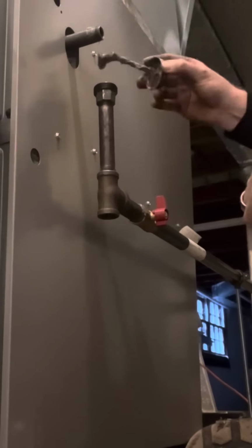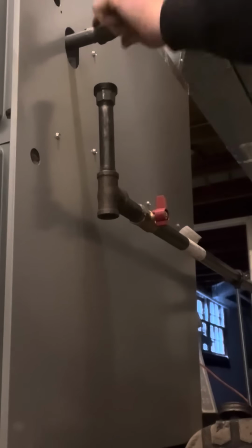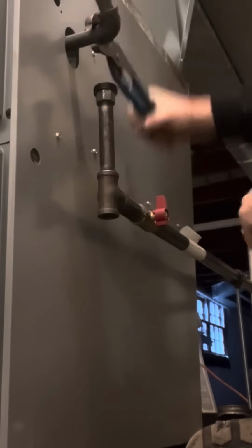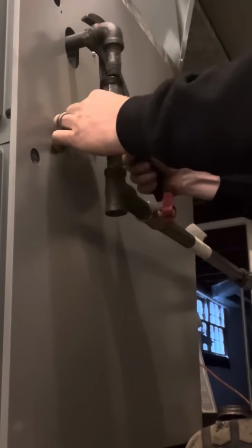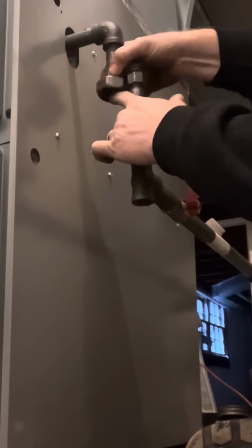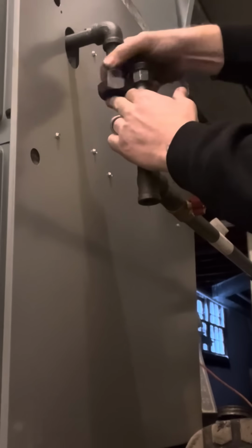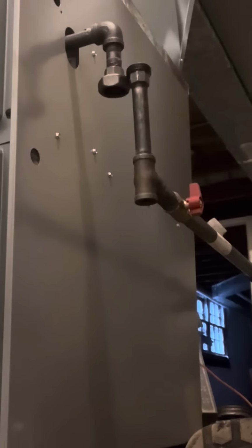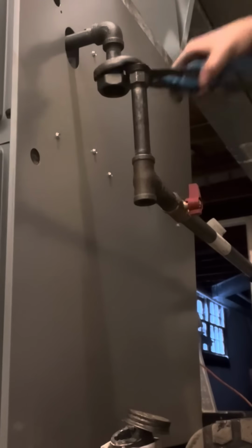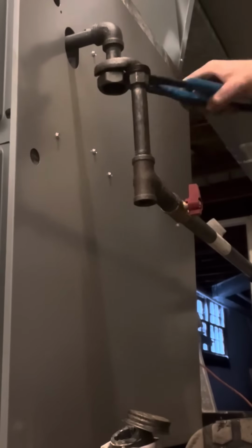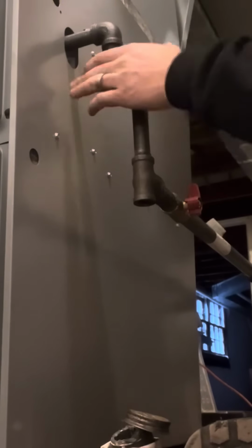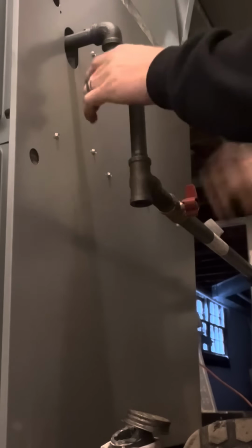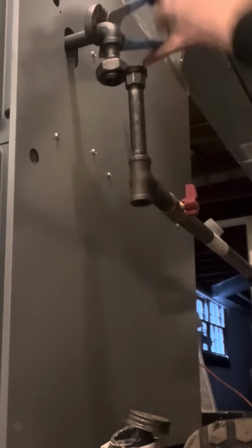Now, moving forward, what orientation should this thing be installed? And I'm going to tell you what the code says. The code says that the sediment trap should be installed on the bottommost portion of the T, and specifically not attached to the branch of the T, or what other people may know as the bull of the T. Meaning you're not supposed to put a sediment trap on a horizontal piece of pipe and then just drop it down, because then the debris and stuff could just jump right over it and wind up in the equipment.